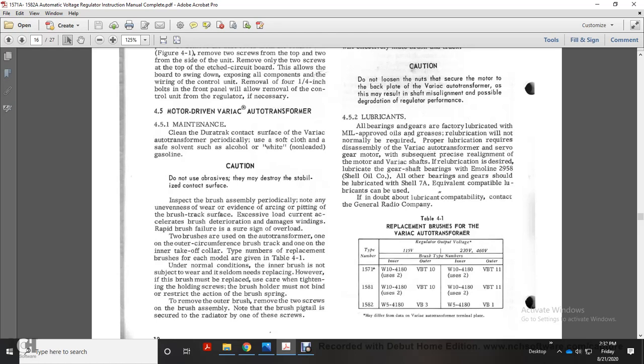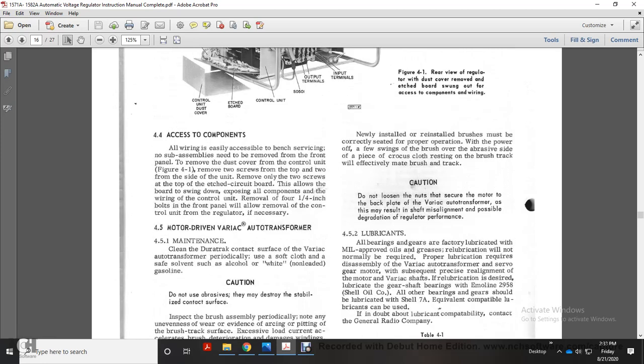There are two brushes on the autotransformer, one over the outer circumference of the brush track, one over the inner take-off collar. The numbers of the replacement brush for each model are given in table 4-1. Under normal conditions, the inner brush does not need replacing. However, if the brush must be replaced, care must be taken with a holding screw on the brush holder, and it must be restrained against the action of the brush spring. Remove the outer brush, remove the two screws of the brush assembly. Note that the brush pigtail is secured under one of these screws.